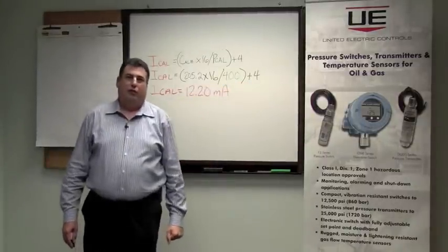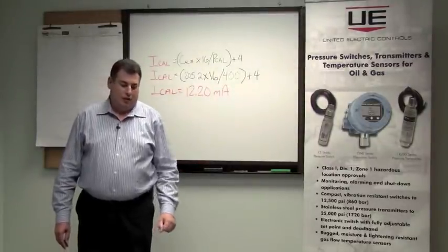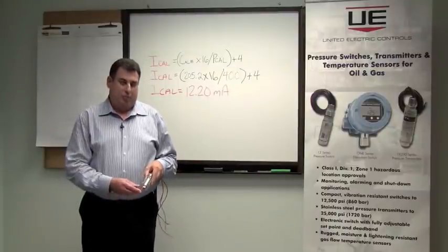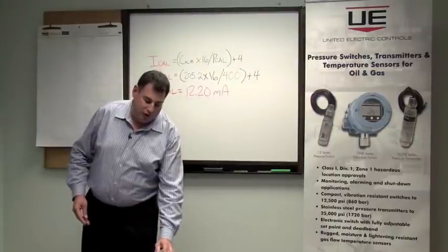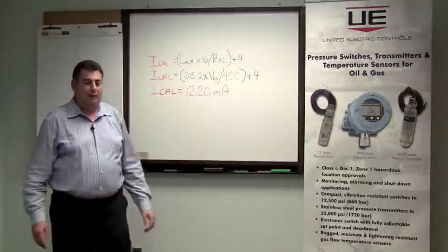The CAL number reflects the amount of the pressure simulated when the shunt CAL is turned on. This is accomplished by connecting the resistor to the sensor, which simulates approximately 20% of the range, and on the 0 to 1000 pound range, 205 is approximately 20%.